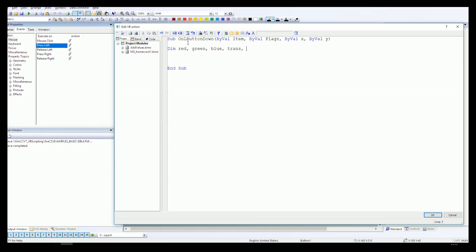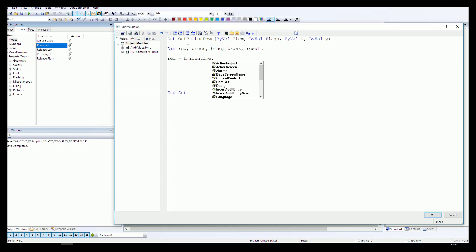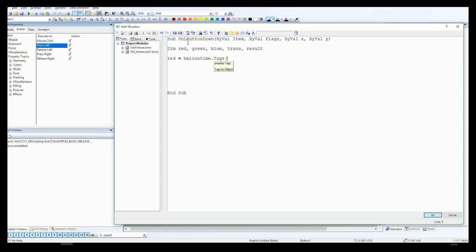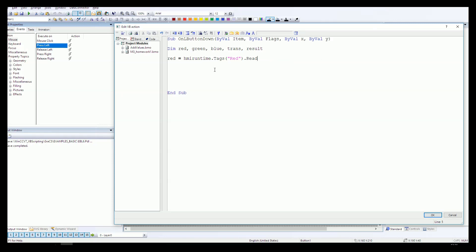I have some internal tags like red, green, blue, trans, and result. Let's first read data from our IO fields. HMI runtime dot tags, now we need to put the name 'red' and we need to put dot read because we want to read data from our IO field. The second one, blue and green, the same.